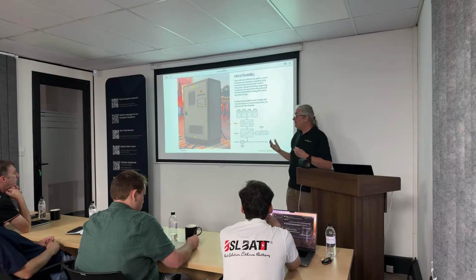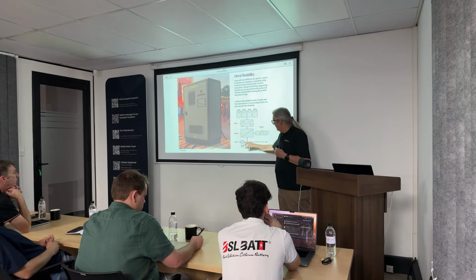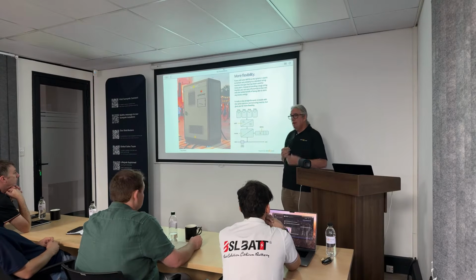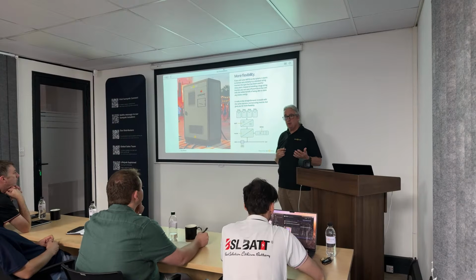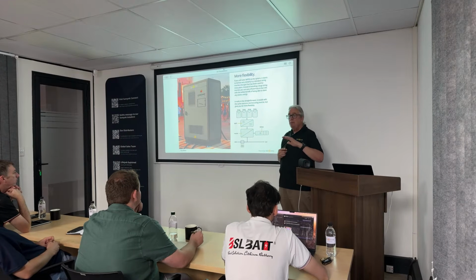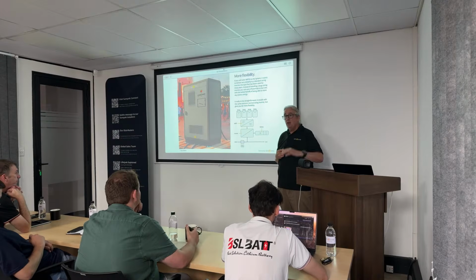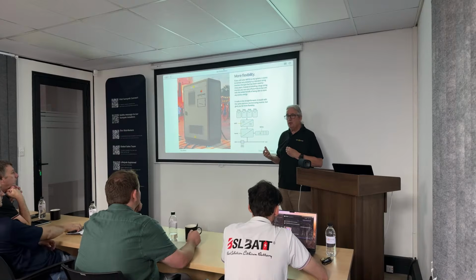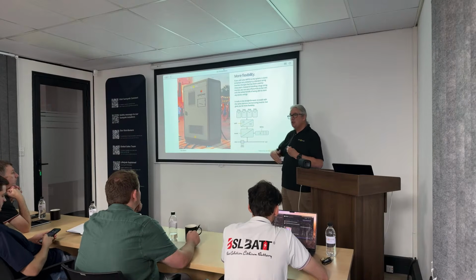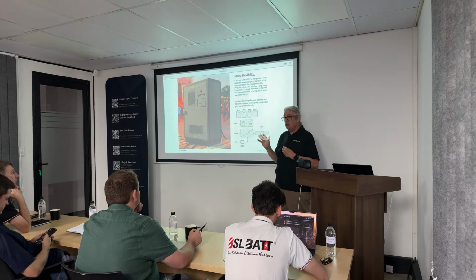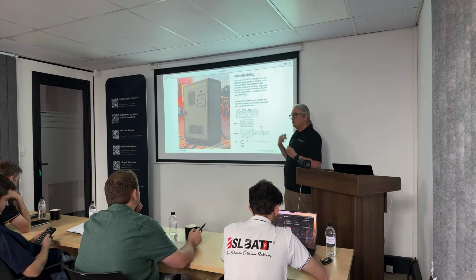It's very, very simple. You notice on here, there's no changeover switch. So basically the static transfer switch, and I'll show you the static transfer switch, is basically a disconnect from the mains. People say, how fast is your changeover? Well, if the inverter is in discharge mode, there's no changeover because you just disconnect on the STS. There's no actual changeover, it's a disconnect. So it doesn't change over.